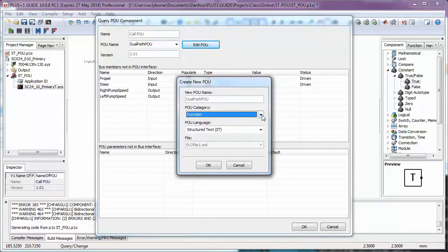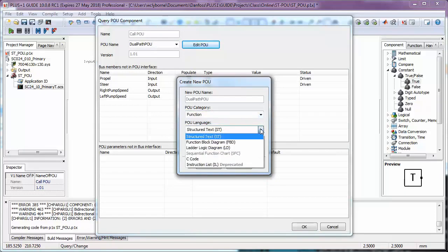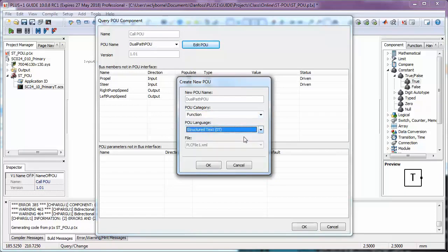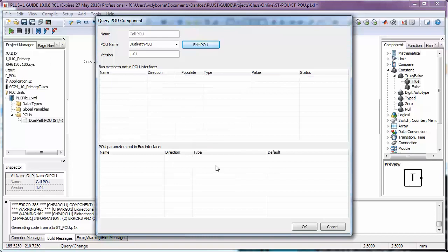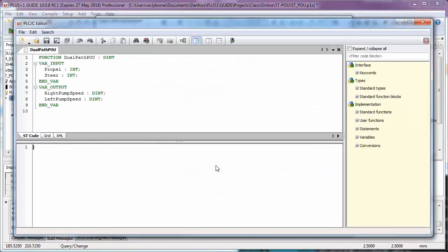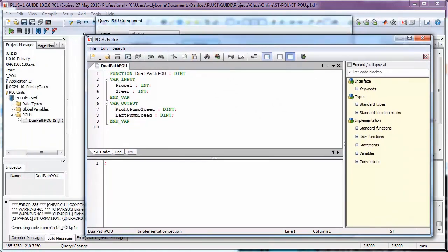We need to tell Guide which of the 61131-3 languages we'll be using, structured text in this case, and whether we are creating a function or a function block. Function blocks are able to remember information since their last invocation, while functions start fresh every time. See the 61131-3 standards for more information about their differences. We'll be using the function type for this demo.